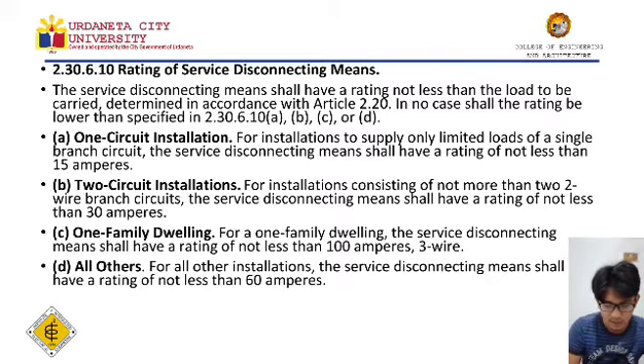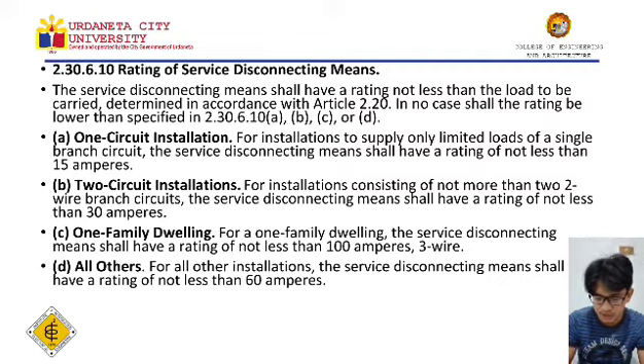So una, ano nga ba yung 1 circuit installation? 1 circuit installation for installations to supply only limited loads of a single branch circuit. The service disconnecting means shall have a rating of not less than 15 amperes. So para sa 1 circuit installation po, mag-supply lamang ng limited load ng isang branch circuit. Dapat magkakaroon ng rating na hindi bababa sa 15 amperes.